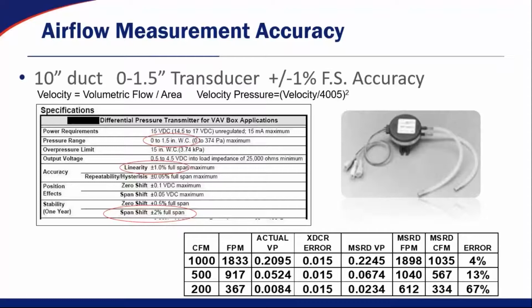So what that attributes to in this particular range, and I apologize, it's kind of an eye chart there on the bottom of the screen, but the pressure range for this pressure transducer is 0 to 1.5 inches water column with a 1% full scale accuracy. So what that 1% full scale accuracy means is 1% of 1.5 inches water column is your fixed error. If you look in the middle of that chart, it says XDCR or transducer error is 0.015. That is 1% of 1.5 inches water column. And that's important to keep in mind.